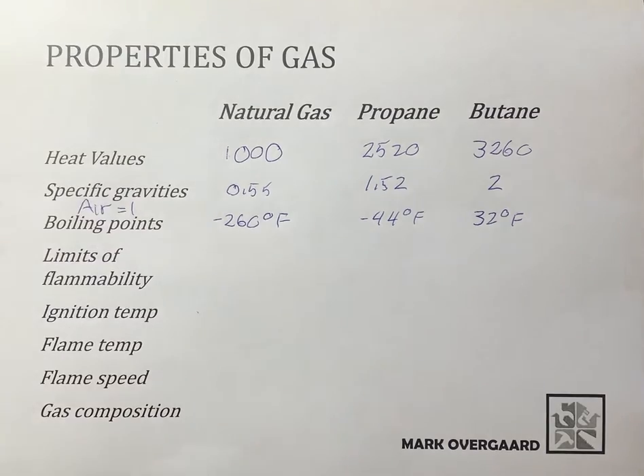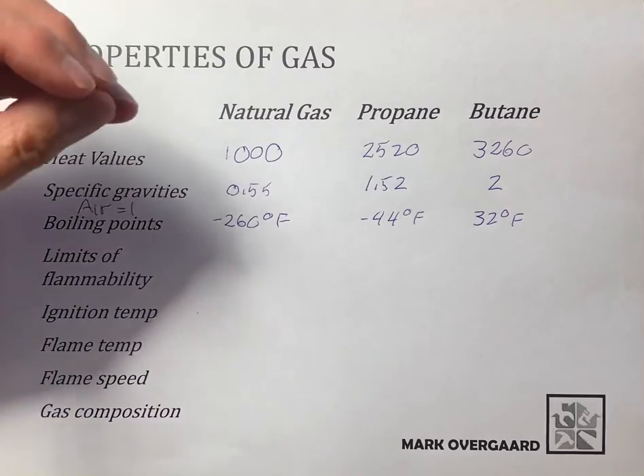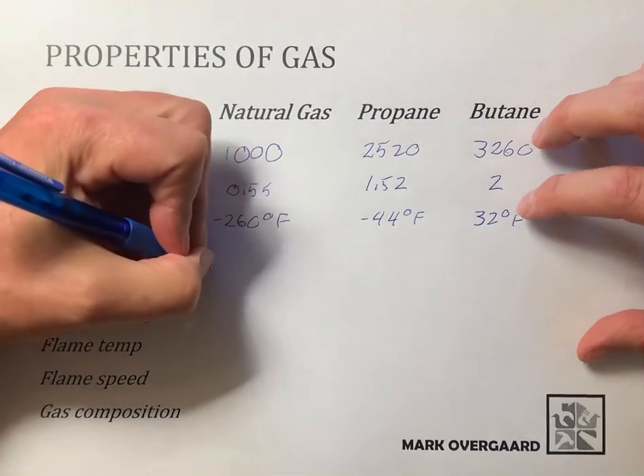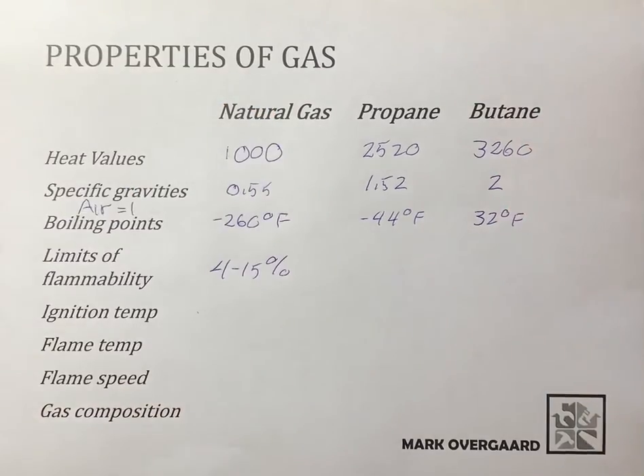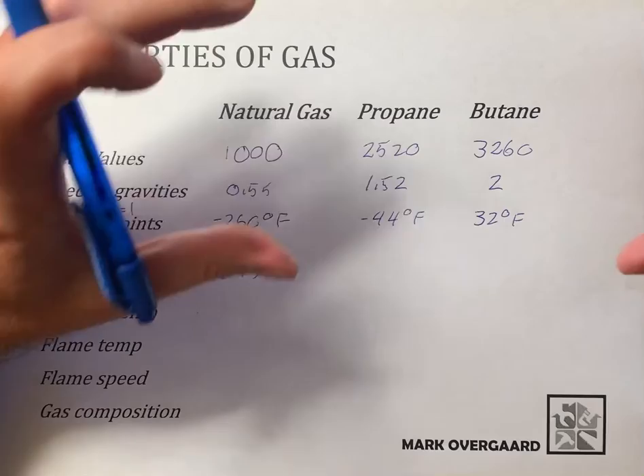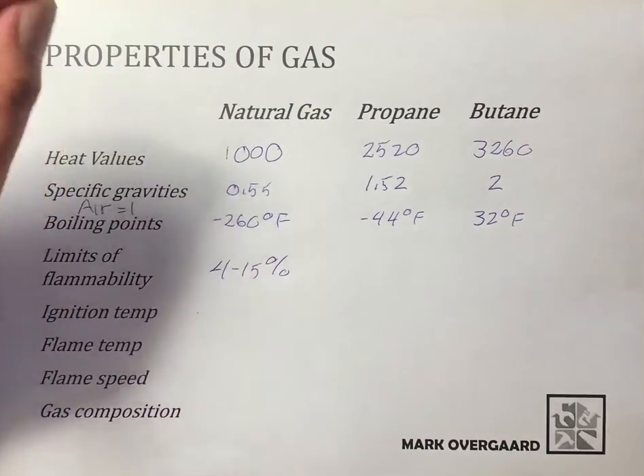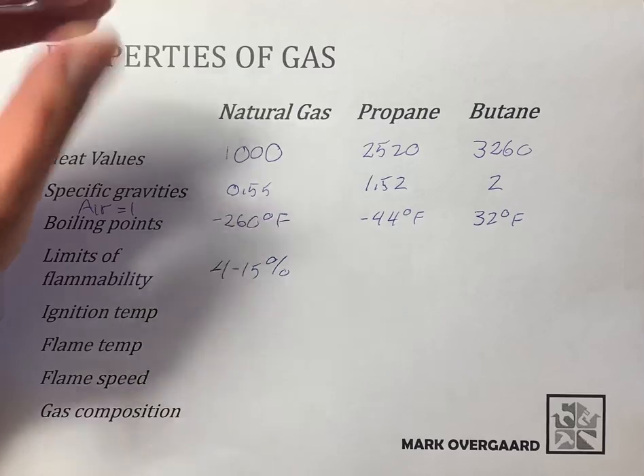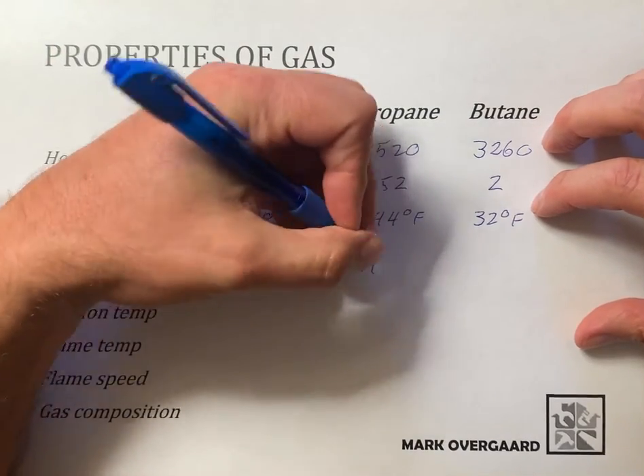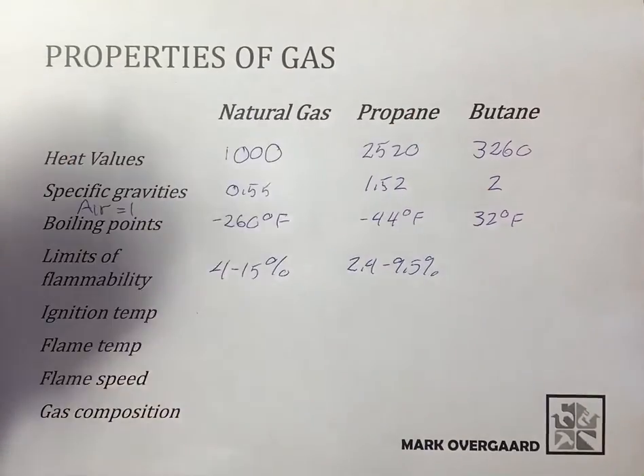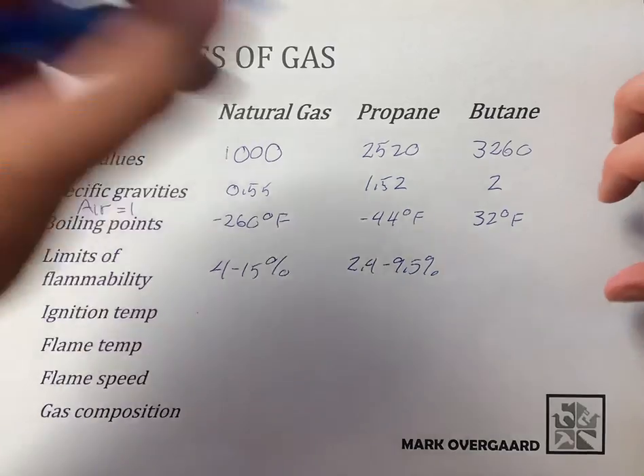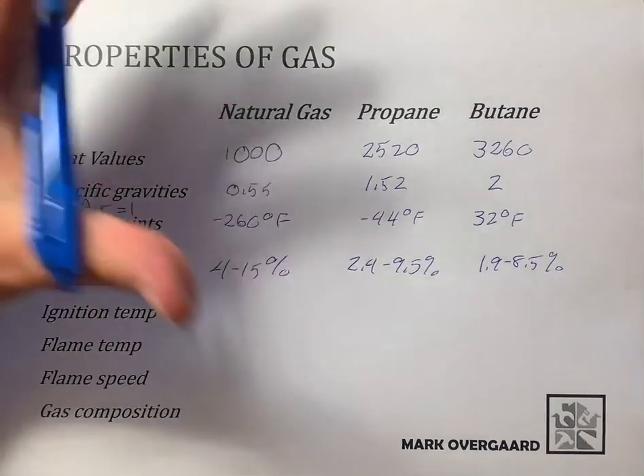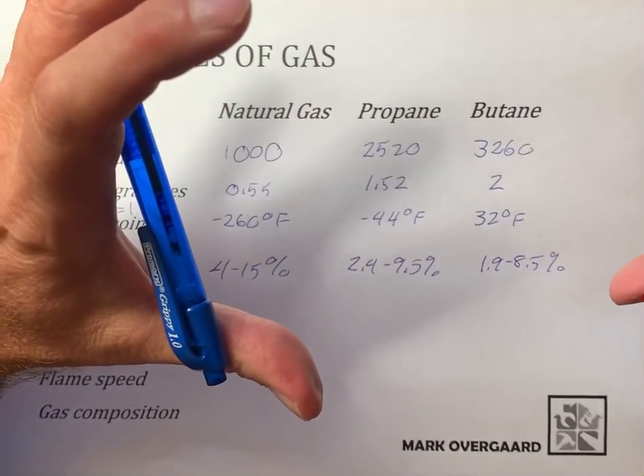Limits of flammability — this is the percentage of gas in air required for combustion. For natural gas it's 4 to 15%, meaning you need between 4% and 15% natural gas in the air for it to combust. That's not a lot to work with, but that's your limits of flammability. Propane is a little less: 2.4 to 9.5%. Butane is even narrower: 1.9 to 8.5% in air for combustion to occur.